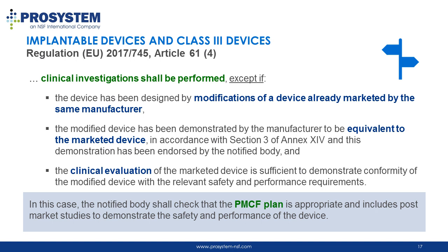In this case, the notified body will check if the PMCF plan is appropriate and includes post-market studies to demonstrate the safety and performance of the device.